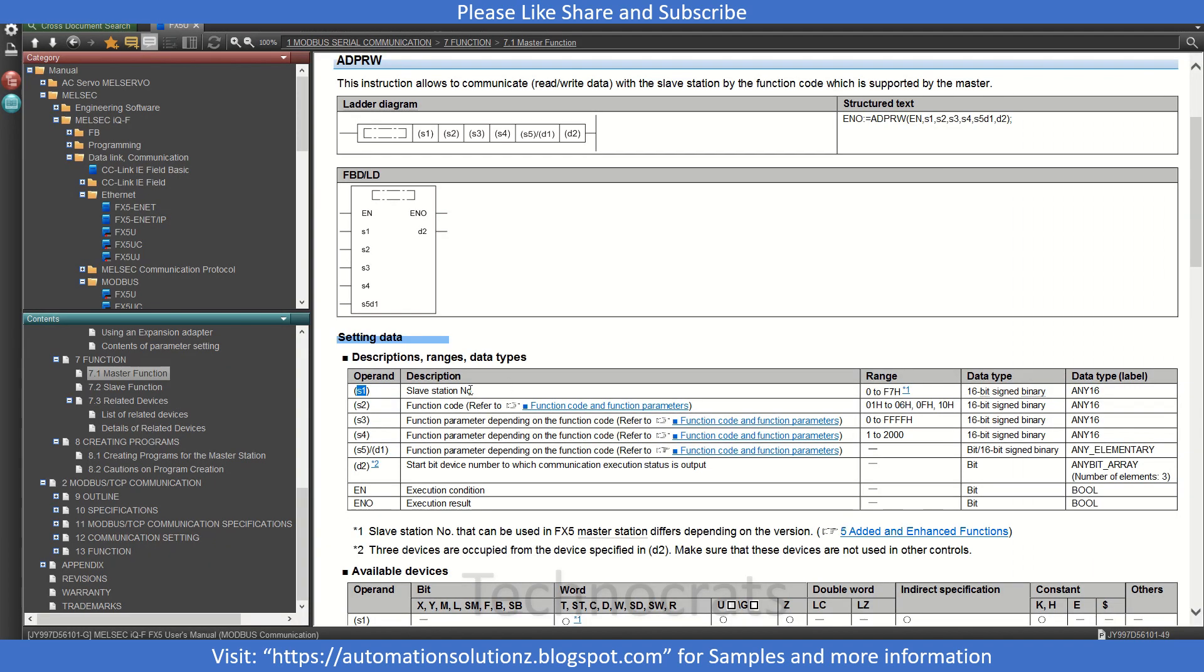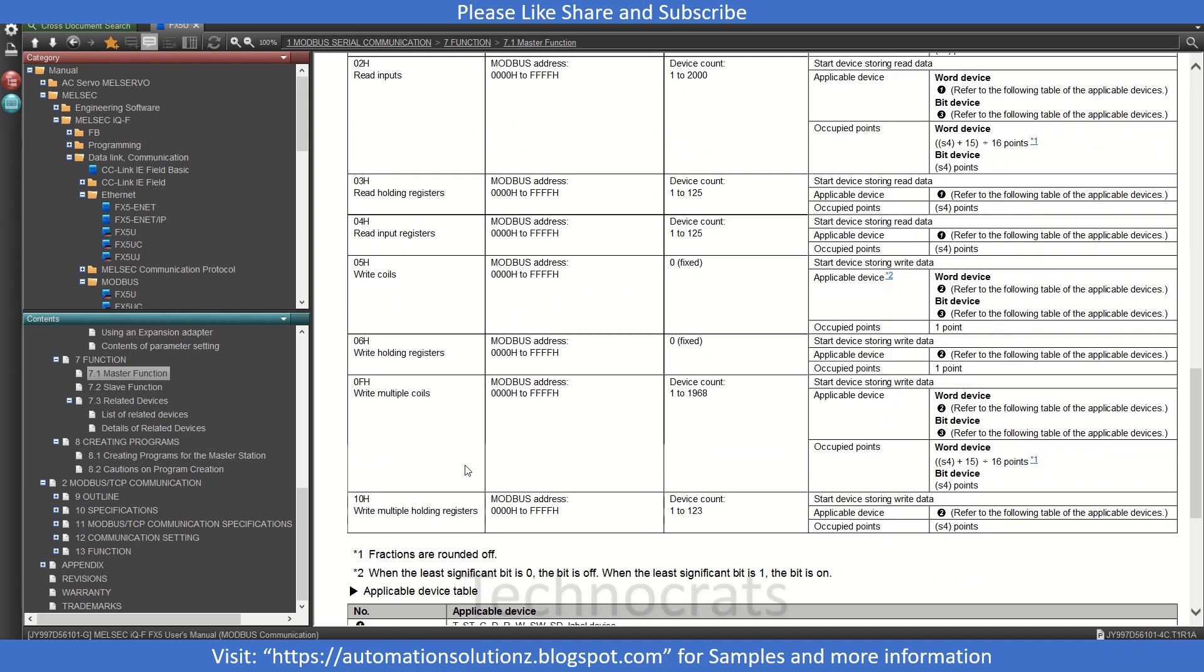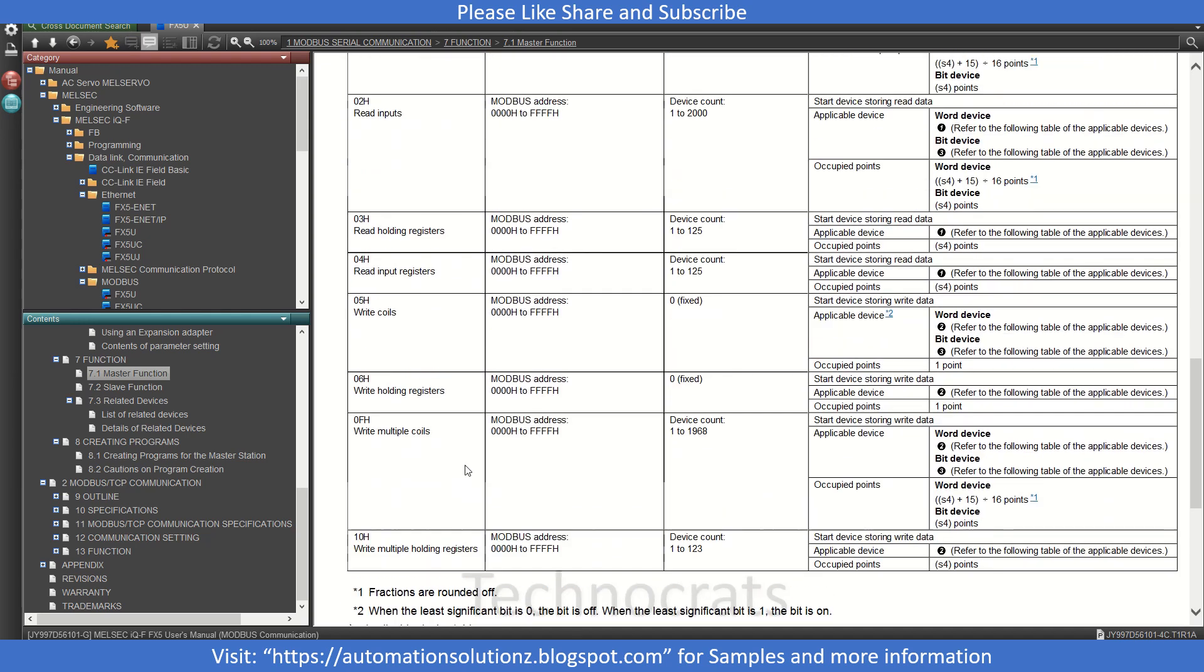Now the second is your function code. Third is function parameter. Let's see the function code and other settings. To read the coil you will write 01, to read the input you will write 02, for reading holding registers you will write 03, for read input 04, 05 is for write coil, write holding register is 06, and so on as mentioned here.